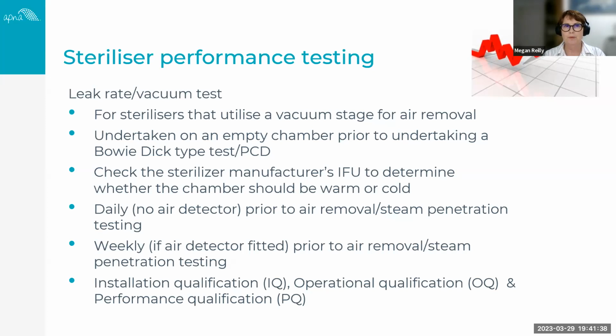And you need to refer again to the manufacturer's instructions, whether it needs a leak rate or a vacuum test. And this is really testing that if you have a sterilizer that uses a vacuum stage for air removal, that is actually working. It's always undertaken on an empty chamber, and it's undertaken prior to doing a Bowie-Dick type test or a PCD if you had a B-class sterilizer. If you don't have a B-class sterilizer, then that second performance test is not required. So again, refer to the sterilizer's manufacturer's instructions to determine whether you need to do this test on a chamber that is warm or cold.